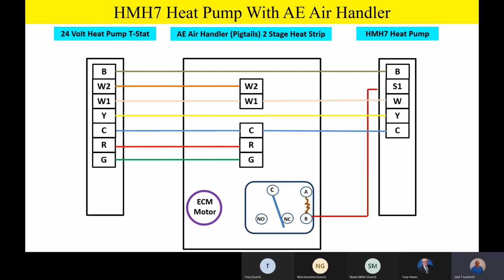Well, let's go ahead and start talking about that relay then. So one side of that relay coil, one side of the single pole double throw relay coil, is going to go up and attach to S1. So when the outdoor unit has the capability, or when it's going to command reduced airflow, let's say when it gets down to like 50% or 60% capacity, it's going to energize that single pole double throw relay, and it's going to reduce the airflow inside to more closely match its point of modulation or capacity reduction. So one side of our relay coil is going to go up to S1, and the outdoor unit is going to generate a 24-volt signal when it's time to reduce airflow.